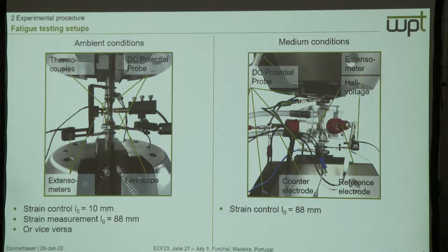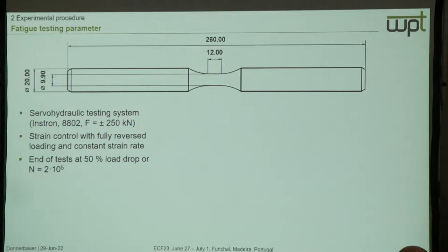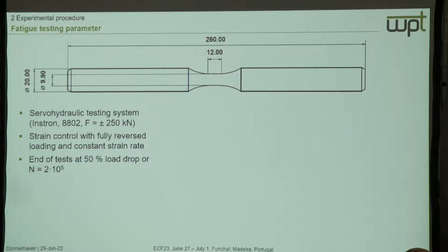At the back of the specimen there is a self-built sensor from one of the project partners making use of the Hall effect. Strain control here is done with the large extensometer. All tests were done with a servo hydraulic testing system with uniaxial load capacity of 250 kN, in strain control with fully reversed loading at a constant strain rate, because the strain rate is known to influence martensitic transformation and therefore the low-cycle fatigue behavior.